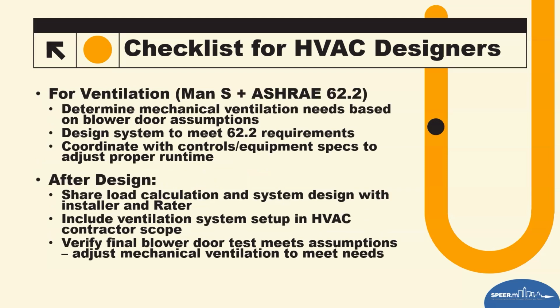And of course, at the same time, you're looking at, well, now that I know the ACH and the building tightness of this, I'm going to use Manual S and ASHRAE 62.2 to determine mechanical ventilation needs based on my blower door assumptions. And then, of course, you design the system meeting the ASHRAE 62.2 requirements. You coordinate with the controls of the equipment and the specs now to adjust proper runtime. This is them just assuming and setting it up as they're installing it.